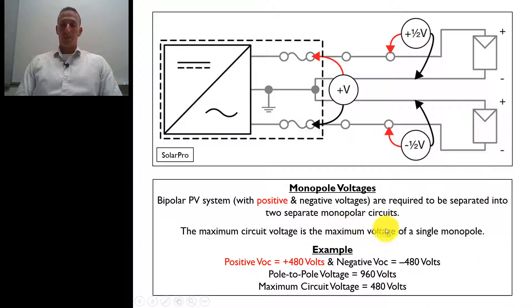The maximum circuit voltage is going to be the maximum voltage of a single monopole. So even though we would have a much higher voltage right here, because these are center tapped and tied to the earth, they're grounded, we're only measuring the voltage of either this or this, and they should be the same as long as these string lengths are the same.